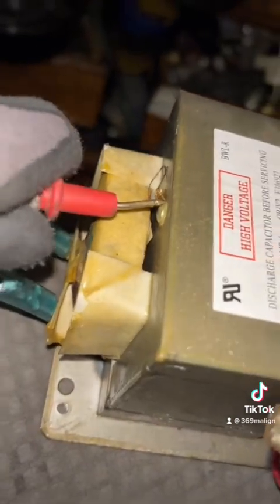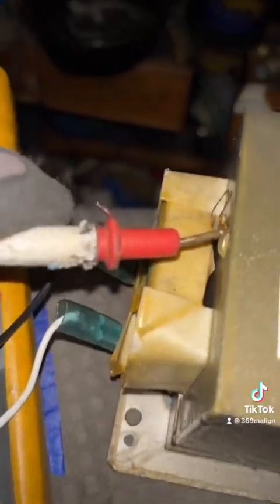We have good continuity there, and when I check it to the frame, we have no continuity, which is what you want - discontinuous. When you check to the frame on the primary, there should be no continuity. So we have no sound, meaning the primary is good. Let's check the secondary.